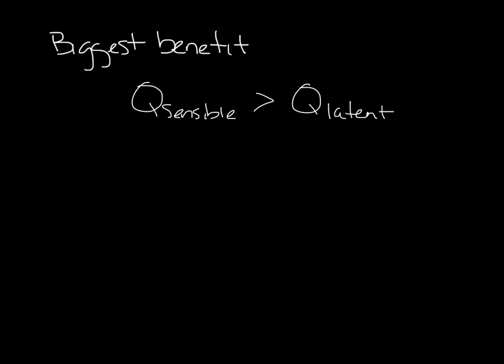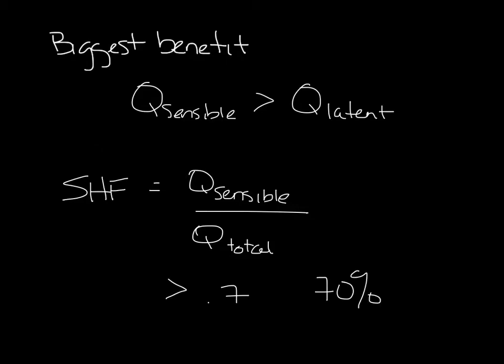So you get the biggest benefits from chilled beam systems when your sensible load is significantly higher than your latent load. Specifically, you want the sensible heat factor, which is the sensible load divided by the total load, to be greater than 0.7 or greater than 70% sensible load.